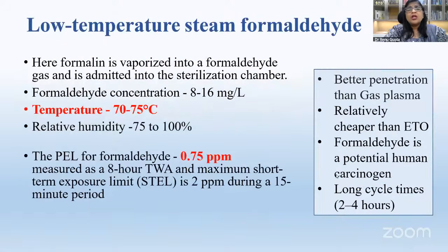Low temperature steam formaldehyde, as the name indicates, in this formaldehyde or formalin, it is vaporized into a formaldehyde gas and is admitted in the sterilizer chamber. So basically you are using formaldehyde gas. Have you ever smelled formaldehyde? When you used to go in your anatomy lectures, that formalin smell, you used to weep like anything. Similarly, in pathology, they keep their tissues. So formaldehyde is again very, very toxic. Carcinogen is there. The use of formaldehyde is decreasing.